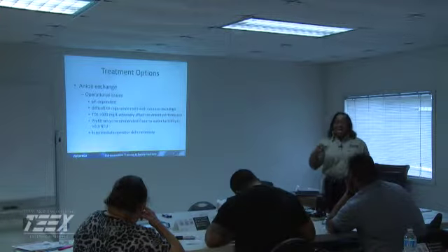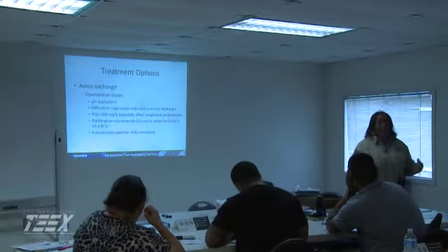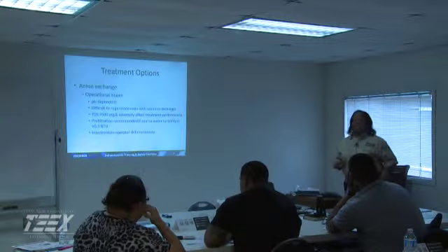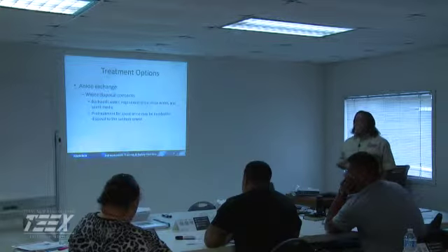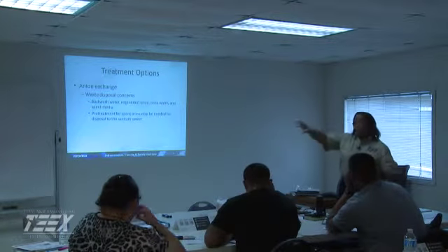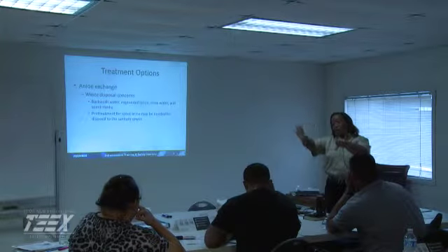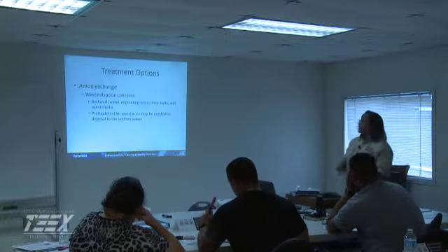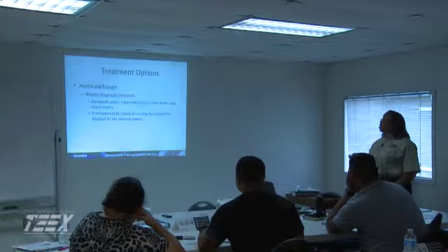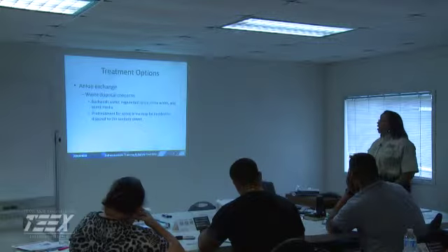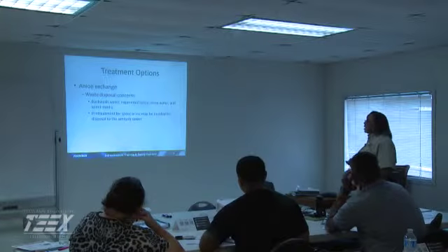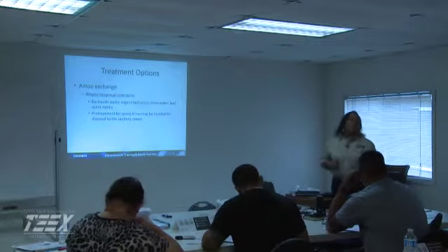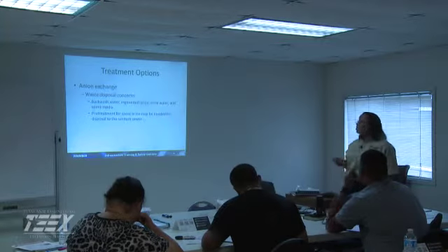Ion exchange, anion exchange, same principle. It's just different charges that we're working with, negative and positive. A negative ion. So the whole purpose is the attraction, negative on one side, positive on the other, they're going to attract each other. We have the same problems as with the aluminum bed: backwash, regenerated brine, rinse water, and spent media issues that you'll have to deal with. And again, pretreatment may be necessary if you have an agreement to put it in your sanitary sewer.